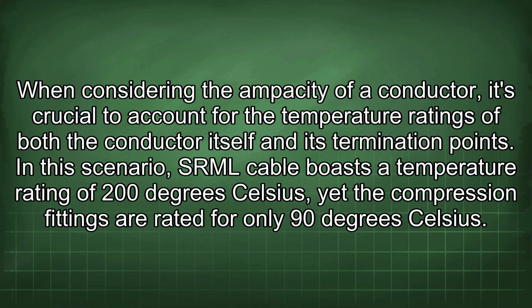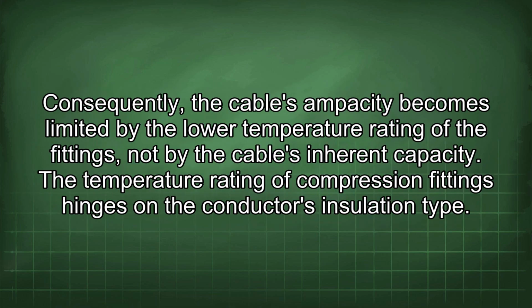When considering the ampacity of a conductor, it's crucial to account for the temperature ratings of both the conductor itself and its termination points. In this scenario, SRML cable boasts a temperature rating of 200 degrees Celsius, yet the compression fittings are rated for only 90 degrees Celsius. Consequently, the cable's ampacity becomes limited by the lower temperature rating of the fittings, not by the cable's inherent capacity.